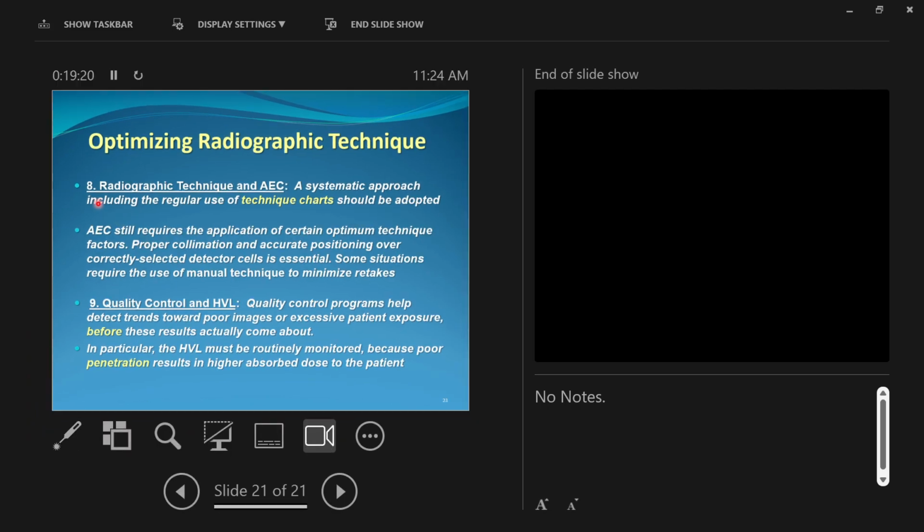The last thing here is AEC. AEC stands for Automated Exposure Control. It's one option of X-ray imaging system. Automated exposure control basically uses fancy electronics to control the exposure your patients receive, making it so you don't have to set the amount of radiation they receive. The computer sets it in real time. It stops the exposure when they've reached enough. Okay.